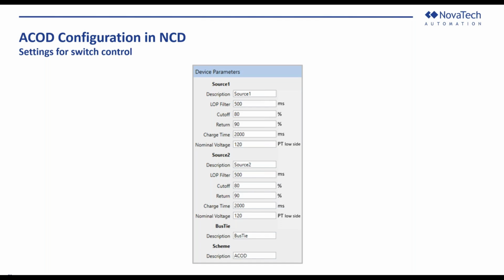Below that, we have the LOP filter. That means loss of potential filter. This is a time window that we are assigning to say I want to make sure that the ACOD is considering potential for this long before operating. This is going to be paired with the cutoff and the return fields that are next. The cutoff is for ACOD recognizing if there is a loss of potential. This is 80%. So if it drops below 80% of the nominal voltage, it needs to have done that for half a second, for 500 milliseconds, for it to consider it a loss of potential and operate on that.